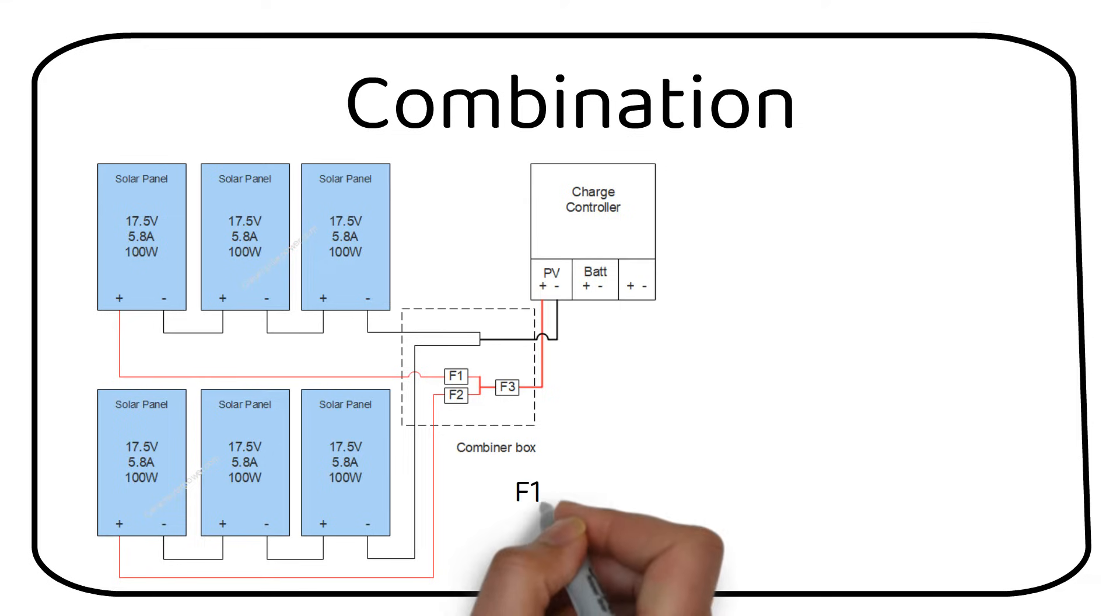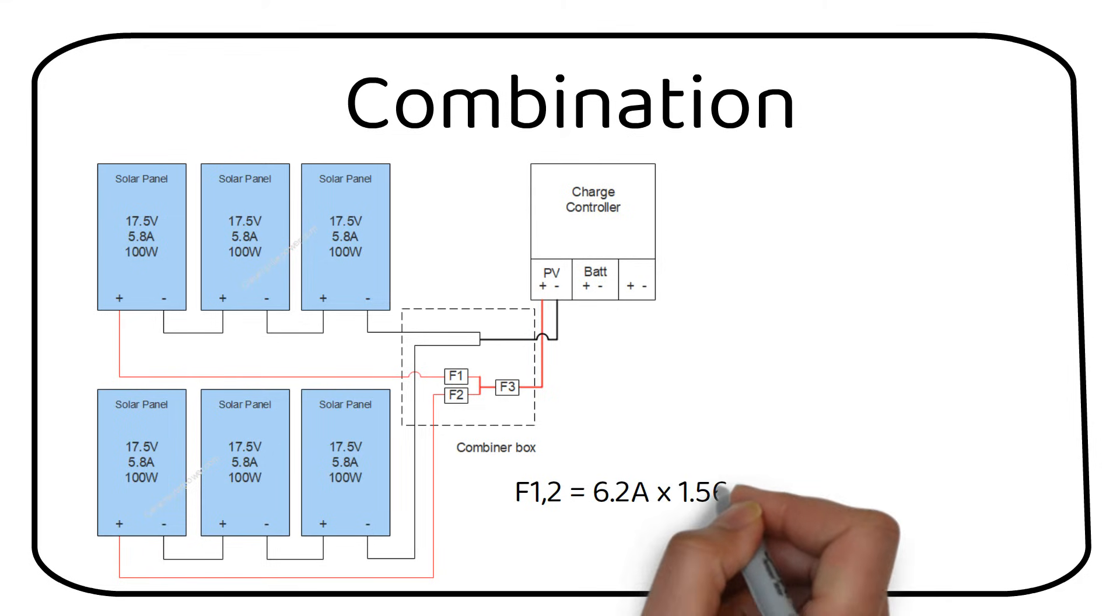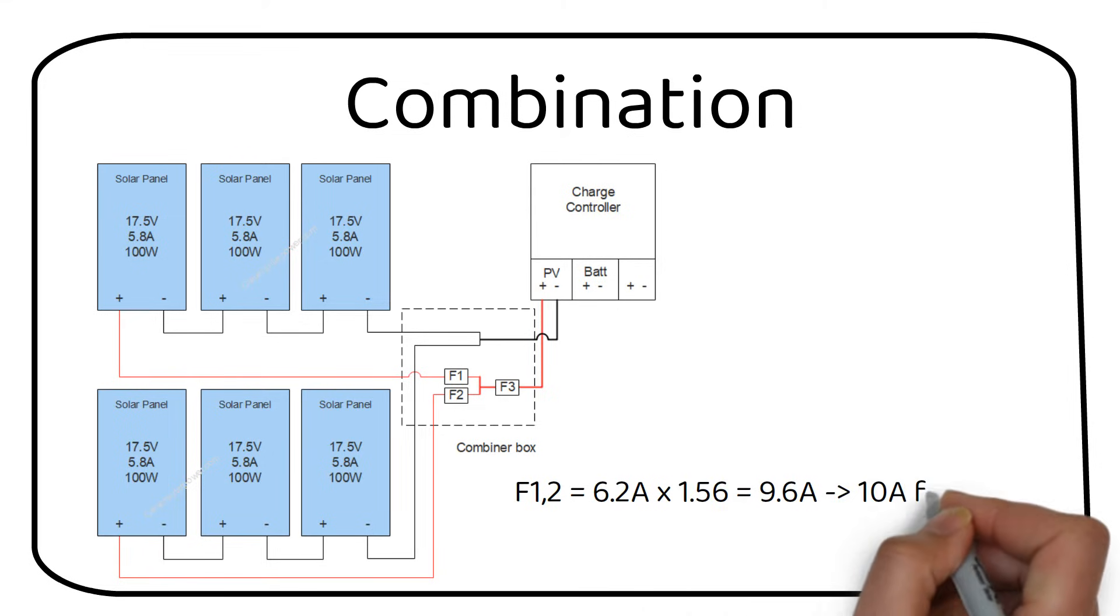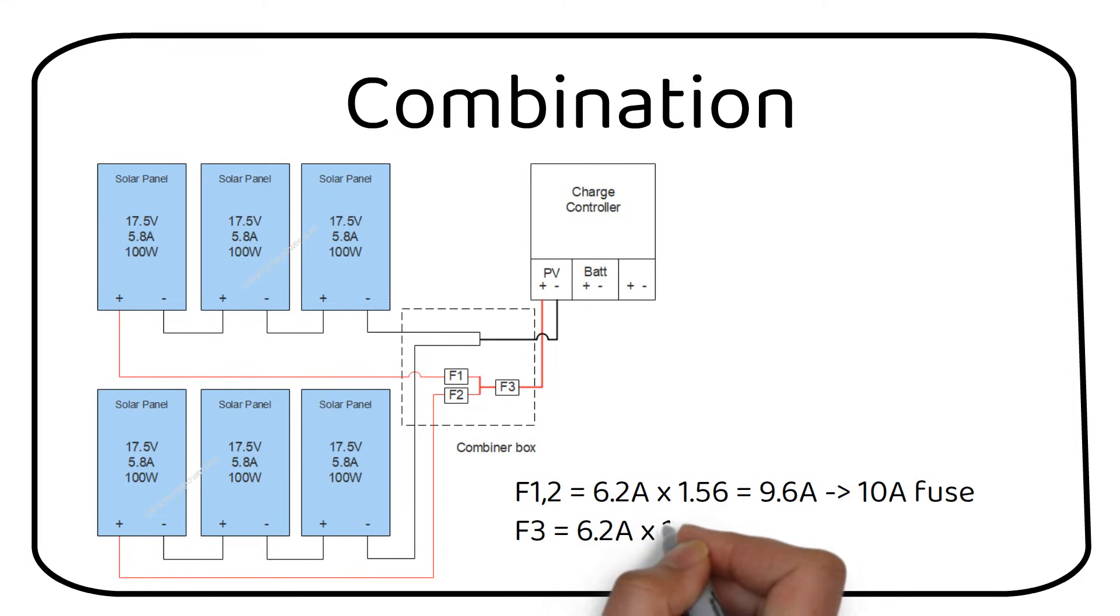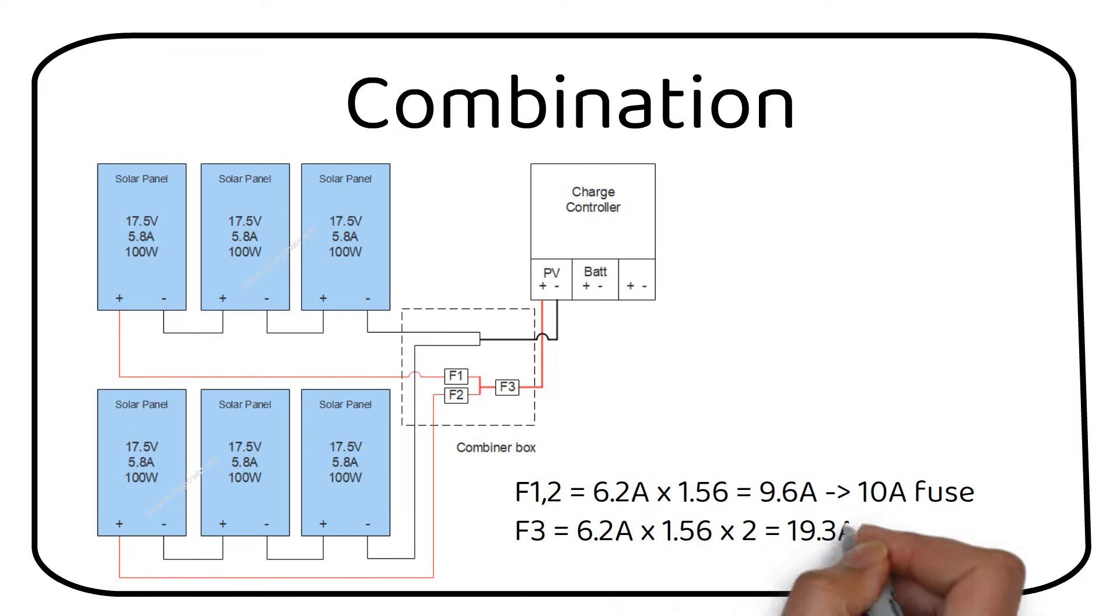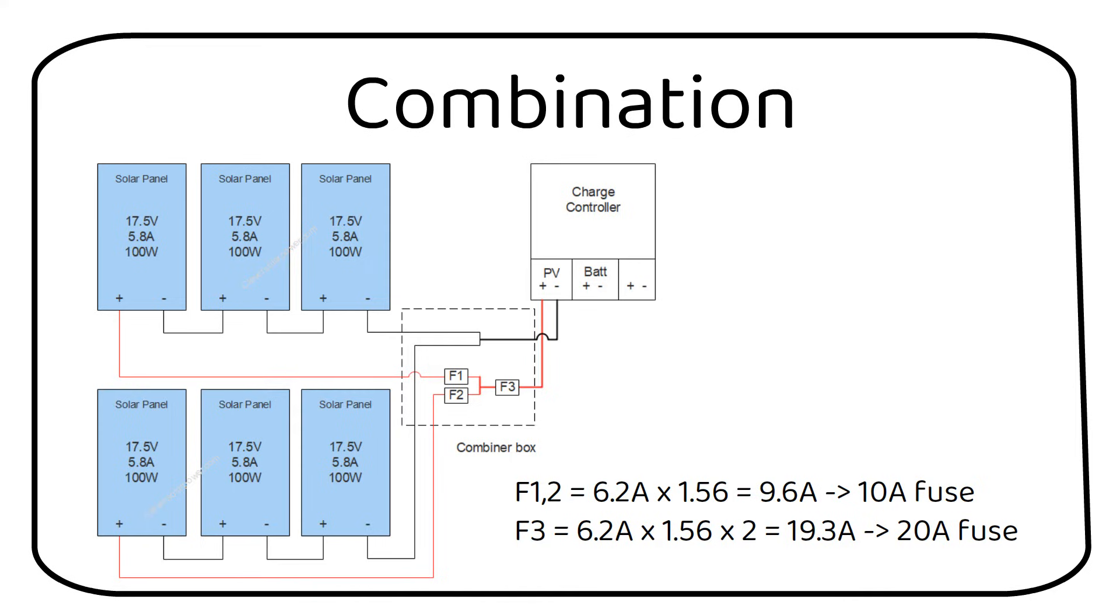We need 3 fuses in total. One for each series string and one for the combined parallel array. Fuse 1 and 2 will be 10A like our previous examples. Fuse 3 will be 6.2A times 1.56 times 2 parallel strings equals 19.3A. We will use a 20A fuse.